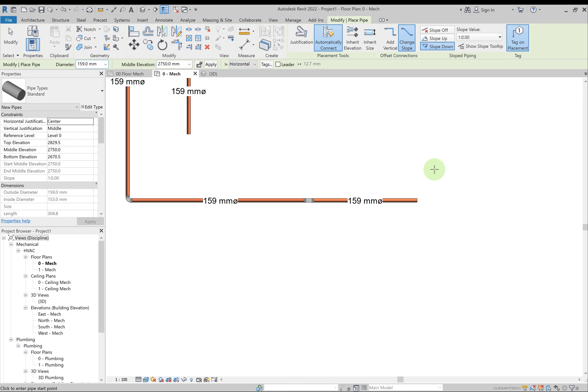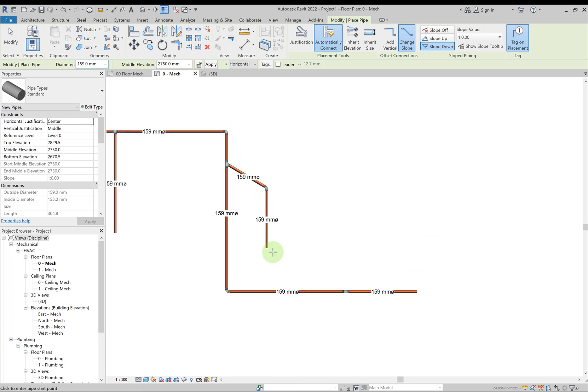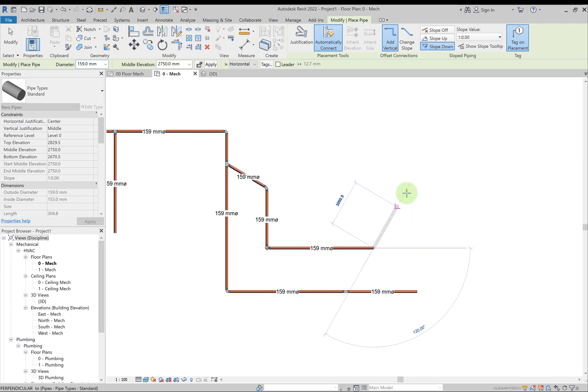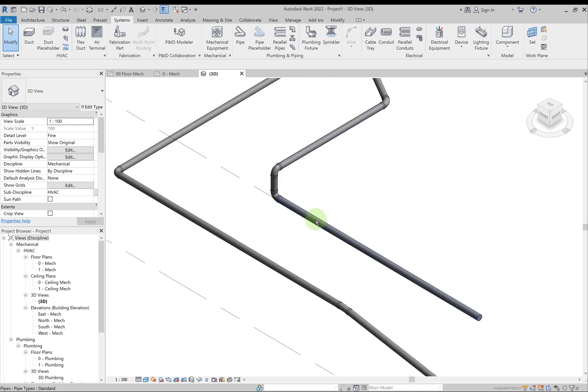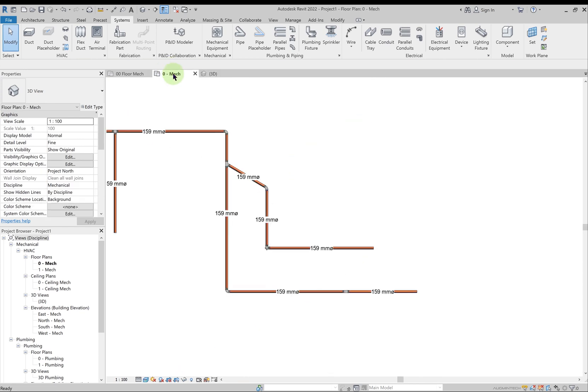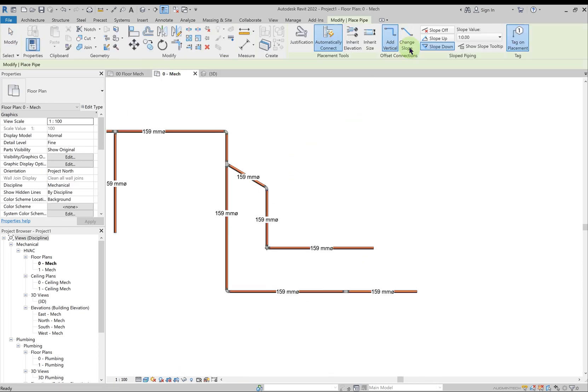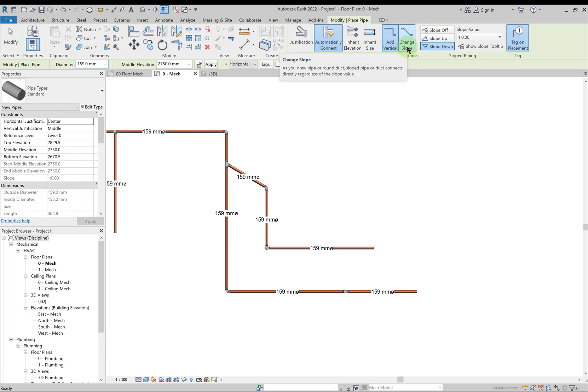Go back to plan view. Let's create another pipe from here at an elevation of 2750, but this time activate the Add Vertical option. Draw a pipe from here — middle elevation is 2750. Go to 3D view and you'll find that these two pipes at different elevations are now connected by a vertical pipe. This is what the Add Vertical or Change Slope options do when joining pipes at different elevations.